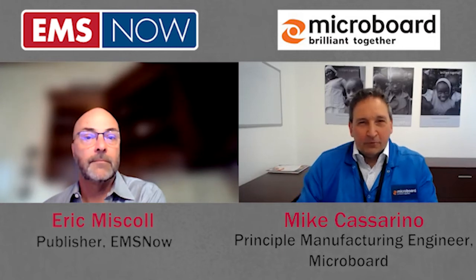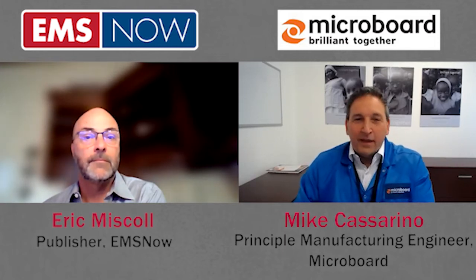You want to make sure the contract manufacturer has a really good quality system that's medical device compliant, and that they actually meet that system, because that's a different thing too. There's been a lot of cases where I've gone to places where I've looked at their quality system on paper and it's great. Then when you actually do your audit and go through the facility, you're like, well, doesn't your procedure tell you to do X, Y, Z? Oh yeah, it does, that person's not here today, so that's why you don't see it. So it's really important to dig in and do that. Making sure you're selecting the contract manufacturer for the right reason is very, very important.